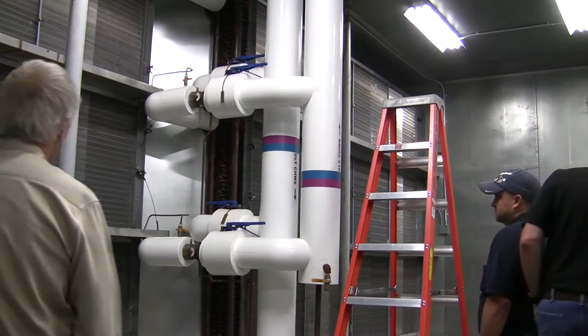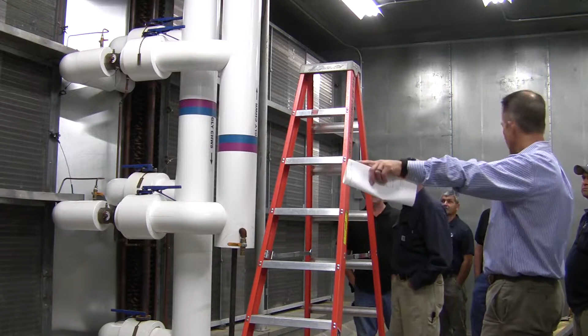So on the coil, we've got four freeze stats, right? One high, one in the middle that kind of wraps to the bottom. So is our coil pretty protected? For the most part, but I'd still worry if we had a lot of outside air. We've got the bottom corners that don't really have a freeze stat on them, and I'd rather see the upper ones a little lower. But in general, we should be pretty covered.